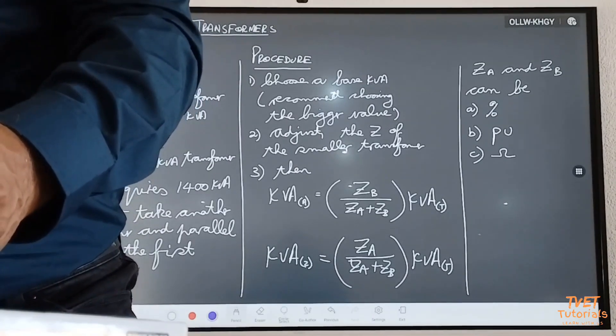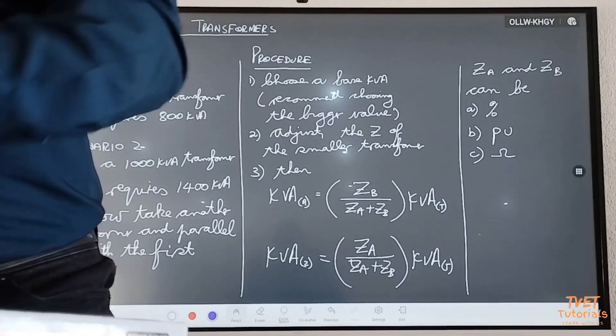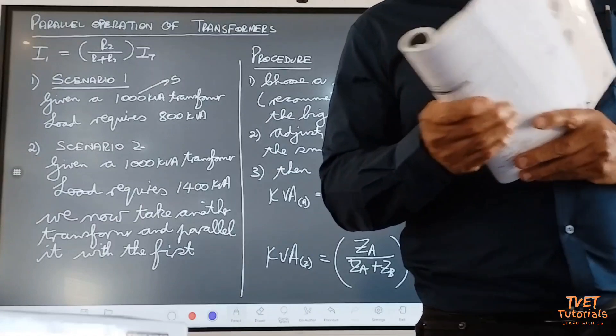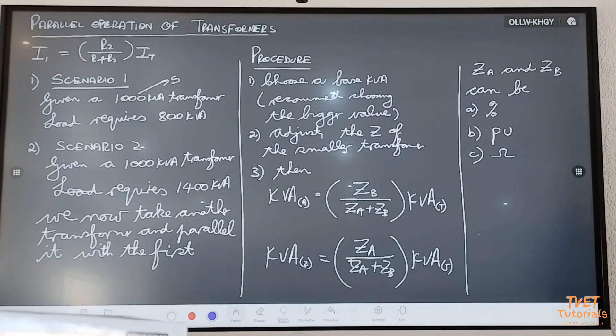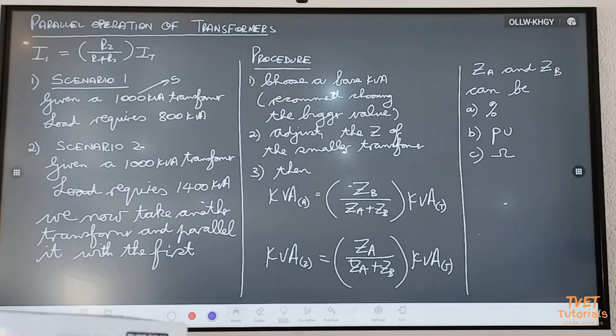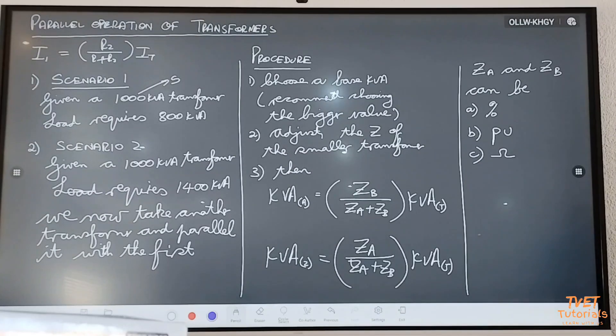Let me go back to my N5 book, page 177. Actually, let's go to page 176 first. Remember — the manner in which I wrote the book is the manner in which I want you to teach. On the left-hand side: load distribution of transformers operating in parallel — that's the grey block. KVA of transformer A, KVA of transformer B — I explained both. Now let's look at the important note. ZA over ZA plus ZB is basically an impedance ratio into which ohmic values, per unit values, or percentage values can be substituted.